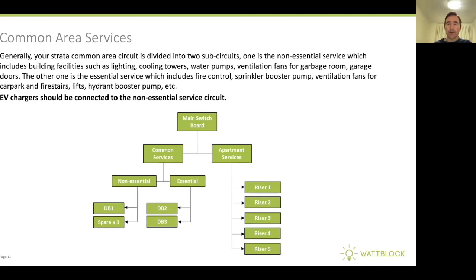Looking at the common services inside a strata building, you've usually got a main switchboard divided into two main sub-circuits. One is non-essential services, which can include building facilities such as lighting, cooling towers, water pumps, and ventilation. The other is for essential services, which includes fire control, sprinkler booster pumps, ventilation fans for car park and fire stairs, lifts, and hydrant booster pumps — all the things you want operating if there's any issue in the building. You'll have distribution boards for both non-essential and essential services coming off the common services circuit.